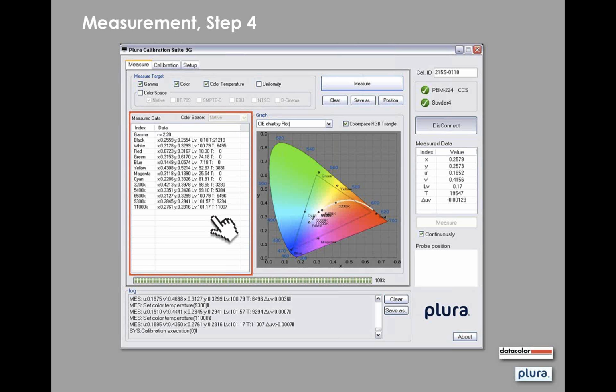Yeah, I would add to that that the jury is somewhat out on 4K and how soon it's going to be upon us, but the color issues, the calibration issues with 4K really don't have to do with color or gamut or gamma or any of the normal functions of a display. They have to do with the huge amount of data that has to be gotten through there and what channel or path it's going to take. So if you have a display like a Plura where you're doing the calibration within the display, that's not a problem. It will communicate automatically. If you're trying to communicate with this display through some new and unique high-speed transfer system from some other solution, then there's no guarantees as to just what data is going to go across there automatically.